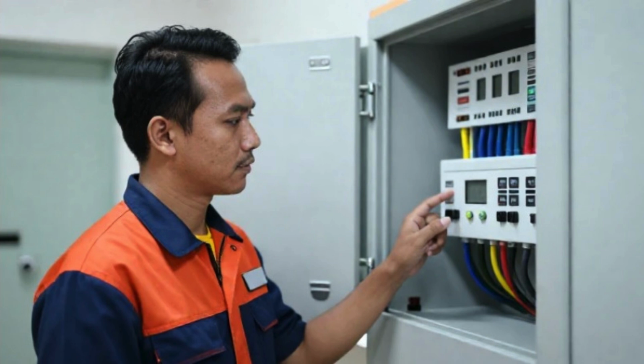Regulatory standards and guidelines provide a framework for ensuring electrical safety in medical equipment. International standards such as IEC 60601-1 define safety and performance requirements for medical electrical equipment.